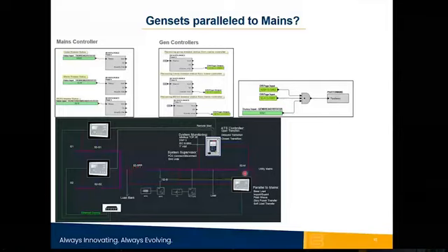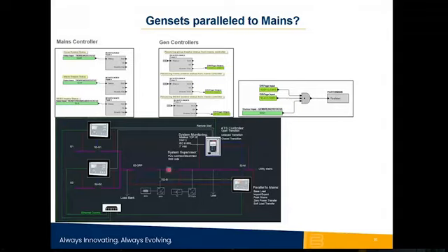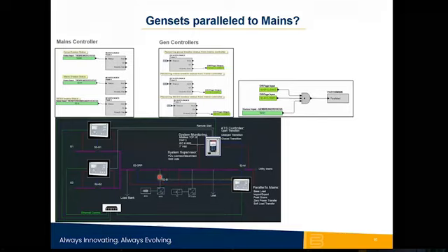Receiving breaker status from the mains and controlling it. In the case of the 52B, the best system breaker, we're not controlling it, we're only receiving the status of it. So the mains controller right here is receiving the status of breaker 1, 2, and 3, the group mains and best system breaker. And it's broadcasting these statuses over Ethernet to the gen controllers.